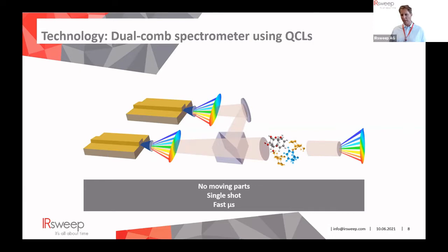Why is that fast compared to other techniques like FTIR spectroscopy? There are no moving parts and very strong lasers, giving excellent signal to noise. It's not just that you can acquire spectra fast — you also get really good SNR. For example, in one microsecond we already get an SNR of roughly 100, which allows single-shot analysis and true microsecond reaction monitoring.